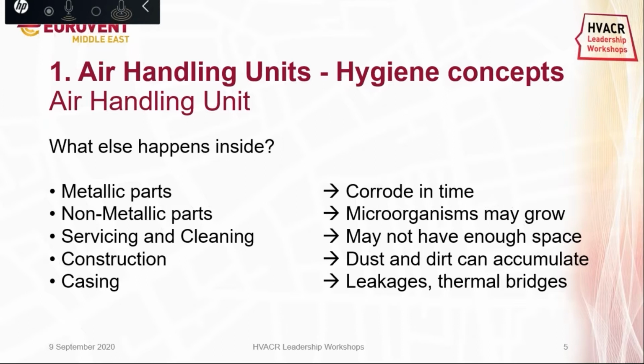Metallic parts may corrode in time. Microorganisms may grow on the non-metallic parts, such as plastics. If a unit is not meant for being hygienic or for a special application, it's usually kept as compact as possible, especially on length of the unit. Then the unit may not always have enough space for servicing or cleaning. Also, its construction could allow dust and dirt to accumulate in some edges or corners or gaps in the unit, in the airflow, and the casing could have risky levels of leakage or thermal bridges. So it doesn't look much hygienic, right?